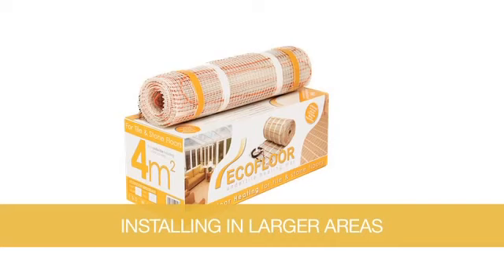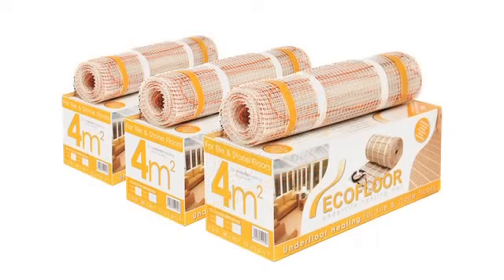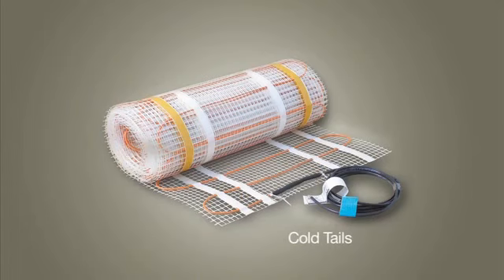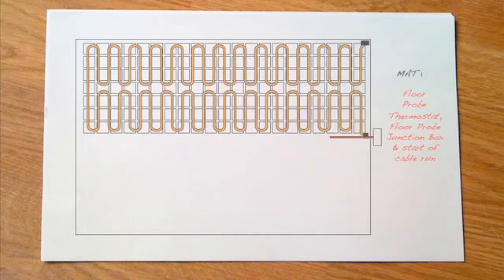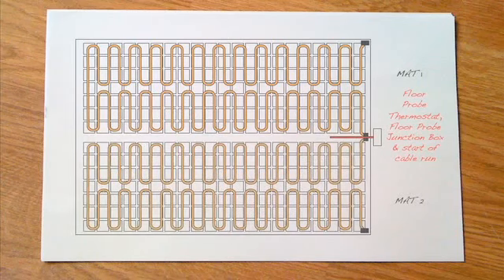The entire floor should be swept clean, taking care to remove any sharp objects. Ensure the subfloor is clean, dry and free from any grease. A heating system for larger areas may require 2 or more heating mats. It is important to note that when installing multiple heating mats, take the following precautions. Plan your installation so that all heating mats' cold tails, the black power cables, terminate in one junction box.